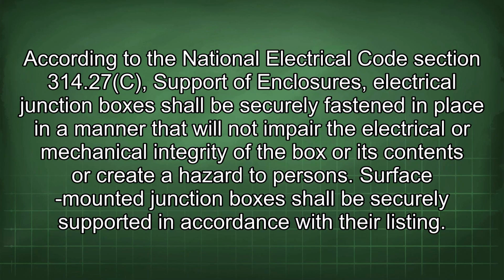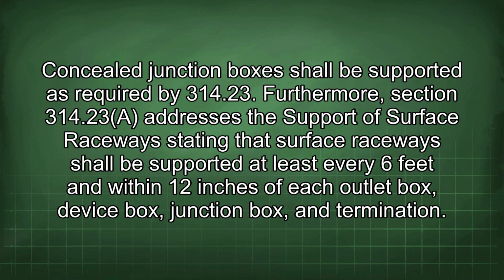According to the National Electrical Code Section 314.27(c), support of enclosures, electrical junction boxes shall be securely fastened in place in a manner that will not impair the electrical or mechanical integrity of the box or its contents or create a hazard to persons. Surface-mounted junction boxes shall be securely supported in accordance with their listing. Concealed junction boxes shall be supported as required by 314.23.